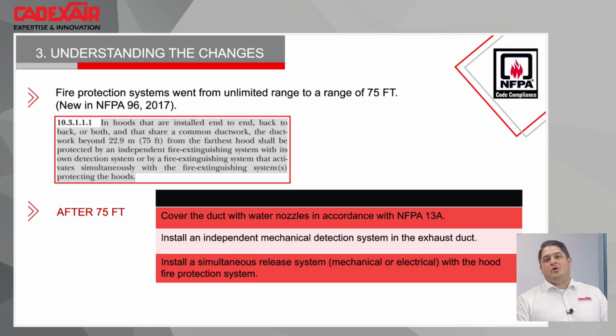Now the problem is, if you go to NFPA 13, many years ago they said, okay, because the ductwork has not been tested after 75 feet, because the UL test stopped at 75 feet, we need to put water sprinklers. That could be a problem, or it's not easy to do. So now NFPA 96, in the 2017 version, because we stepped from the 2014 to the 2021 version, they still have a new one in between, the 2017. So they ask that when you've got hoods on the same exhaust fan, you cannot cover more than 75 feet of ductwork, and you need to have a simultaneous operation system or an independent fire protection system to cover the next 75 feet.